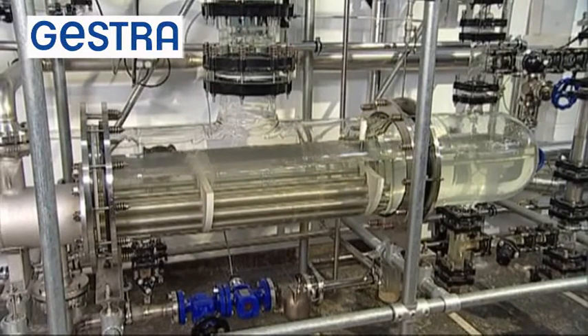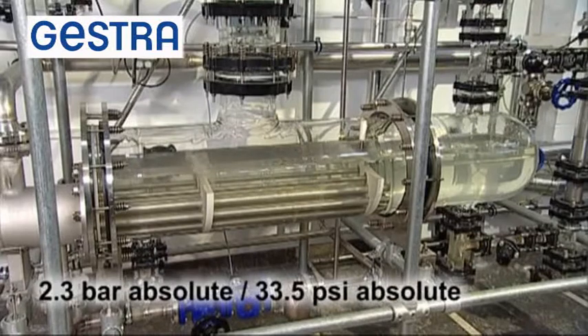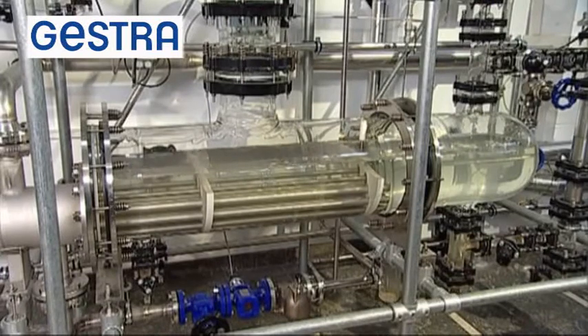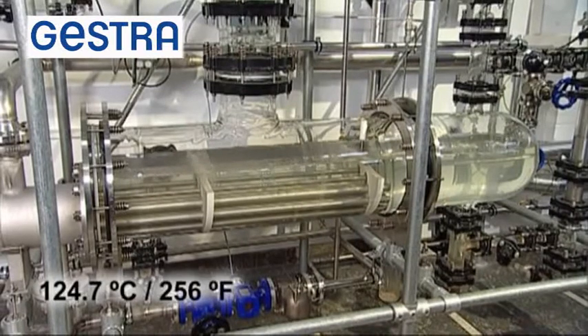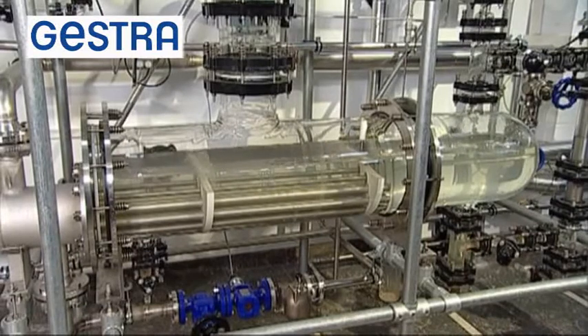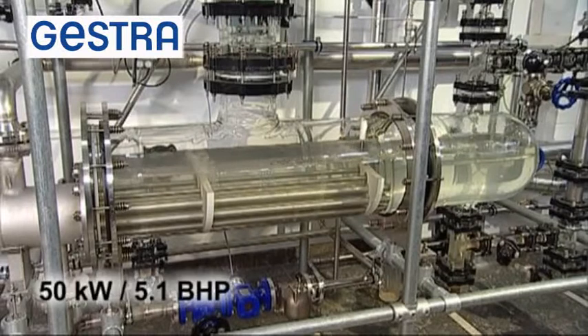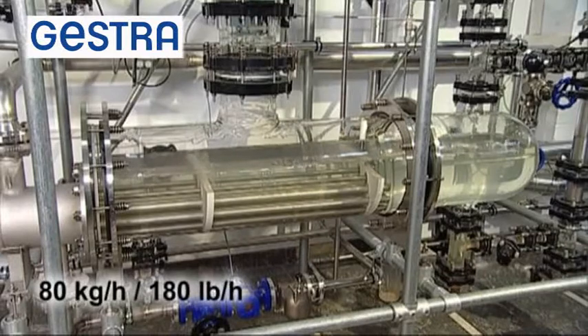This video shows the thermal processes taking place during the generation of saturated steam in a glass steam boiler. This is demonstrated with the aid of the glass evaporator built by GESTRA AG Bremen. The evaporation process occurs at an operating pressure of 1.3 bar gauge, which corresponds to 2.3 bar absolute. At this pressure, the boiling point as well as the saturation temperature are 124.7 degrees centigrade. The capacity of the steam boiler is 50 kilowatts, which yields a steam flow rate of 80 kilograms per hour.